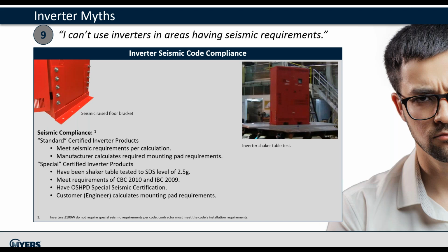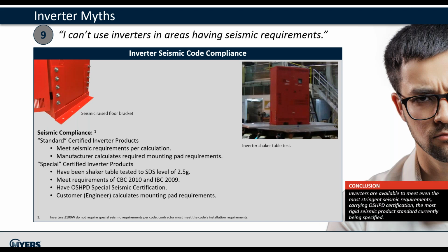OSHPD seismic ratings are certifications performed at a laboratory by mounting the entire unit, including batteries, on a steel deck and shaken in the X, Y, and Z planes to a specific level, which is determined by the target zone in the county and the height that the equipment will be located. The equipment must survive the test and be fully functional after the test. Summary is that the Myers EPS inverters have been tested to the most stringent seismic levels, allowing them to be put in any location in the U.S.